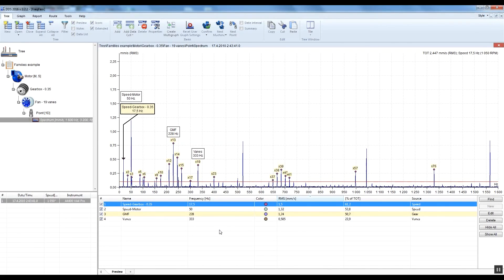The frequency displayed in the second column is the carrier frequency of the family. The RMS value is the sum of the carrier RMS and all modulation RMS. Harmonics and sidebands are the modulations. The RMS percentage value is the proportion of the family RMS to total spectrum RMS. The sum is not equal to 100% — this is correct because many peaks are contained in more than one family.